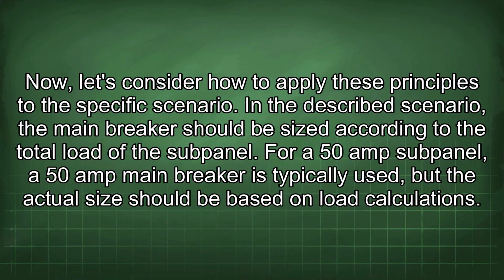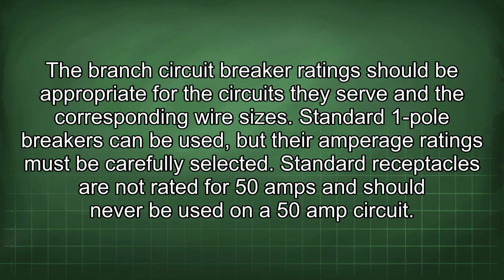Now, let's consider how to apply these principles to the specific scenario. In the described scenario, the main breaker should be sized according to the total load of the subpanel. For a 50 amp subpanel, a 50 amp main breaker is typically used, but the actual size should be based on load calculations. The branch circuit breaker ratings should be appropriate for the circuits they serve and the corresponding wire sizes. Standard 1-pole breakers can be used, but their amperage ratings must be carefully selected.